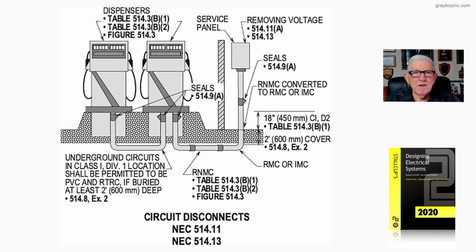So if you look at 514.11(B), as in boy, you're looking at an attended type service station, and then of course you would place those within, say, I think 20 foot, from 20 foot up to 100 foot. Unattended, then it gives you the rules in (C).